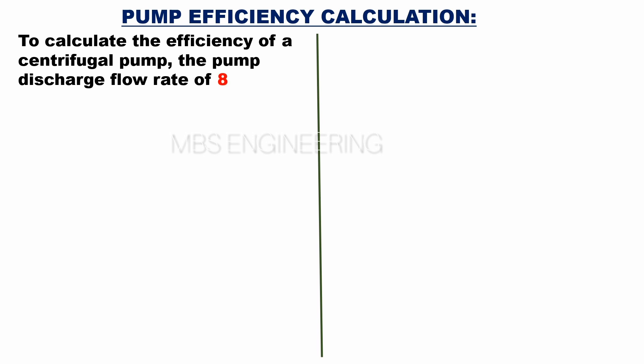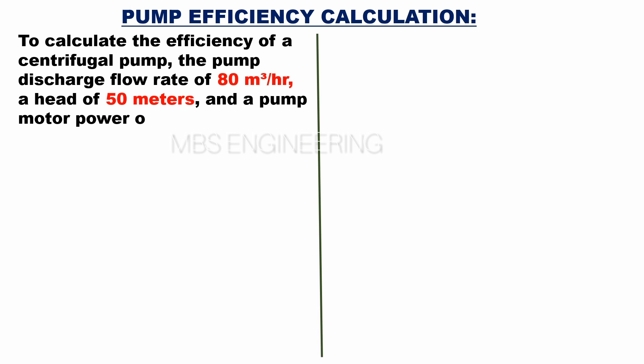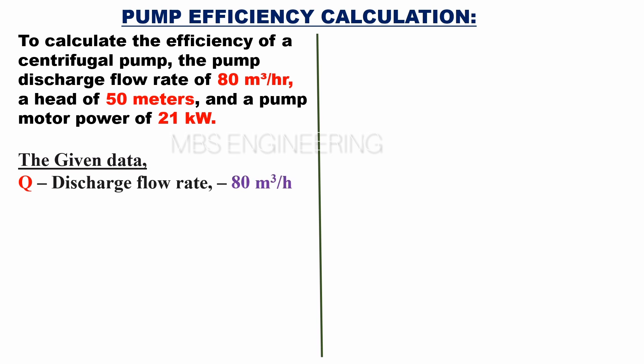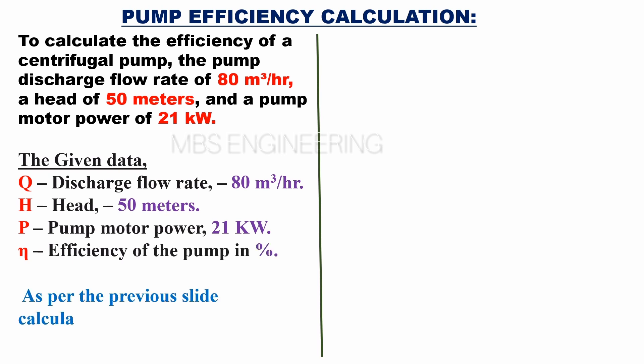We will now calculate the efficiency of the centrifugal pump. Given: pump discharge flow rate of 80 cubic meters per hour, a head of 50 meters, and a pump motor power of 21 kilowatts. Eta is the efficiency of the pump in percent. As per the previous slide calculation, brake kilowatts is 14 kilowatts.